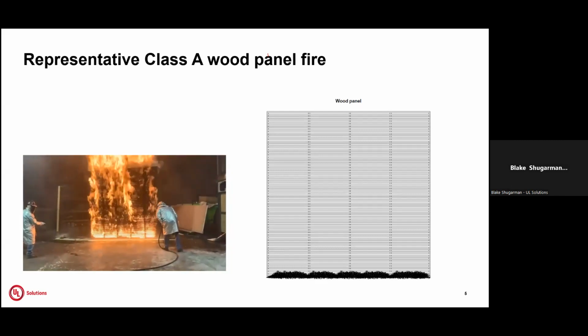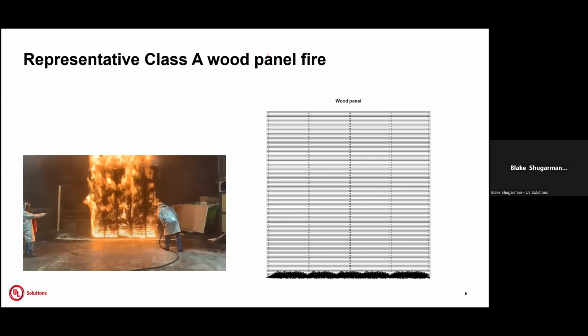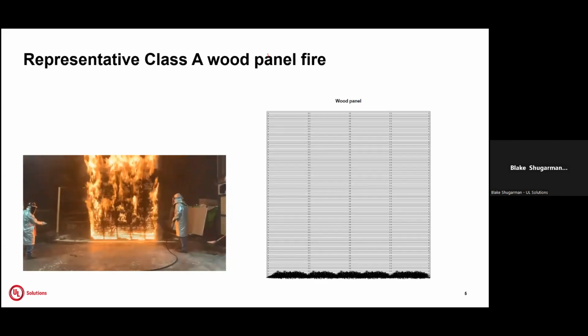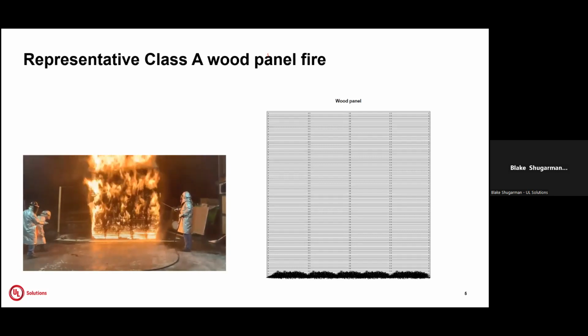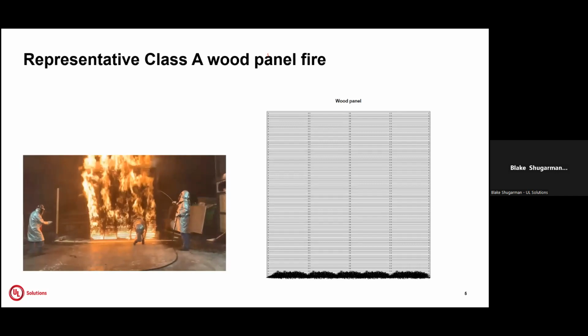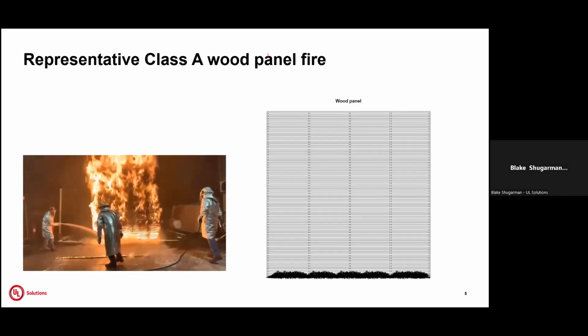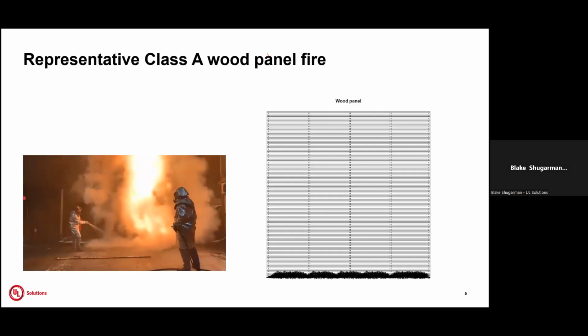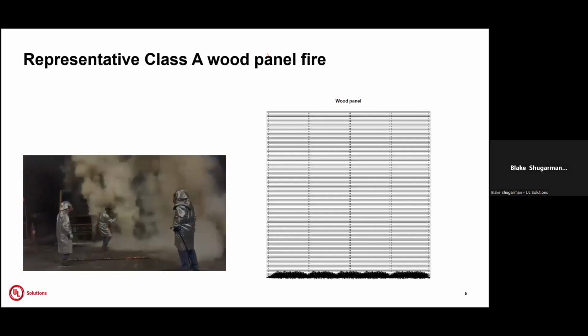And now we see that the other technician has noted some cracking of one of the wood sticks, which is not permitted for the fire test. It is permitted to remove the broken stick, which the other technician is coming in and doing now. The extinguisher agent is applied rather quickly, and the fire is extinguished.